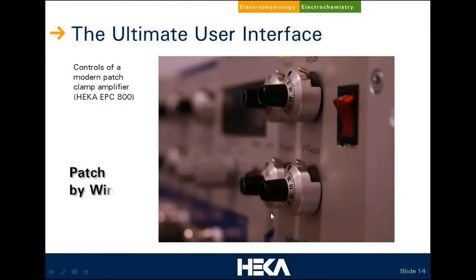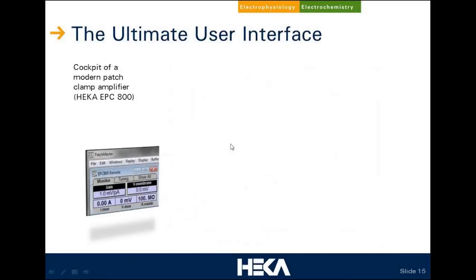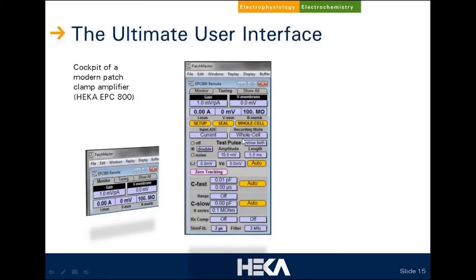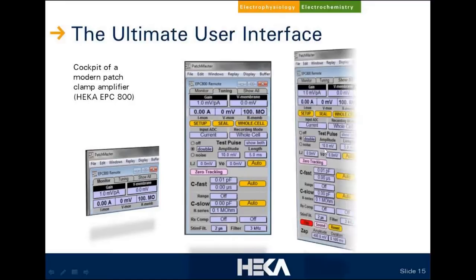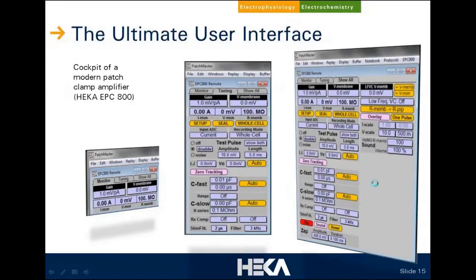Translating that to a patch clamp amplifier: patch-by-wire means you have what looks like an analog control with knobs and buttons, but it controls digital circuitry behind the scenes. That's the old-world interface. The new-world interface of that same amplifier is the cockpit of a modern patch clamp amplifier — the EPC-800. It comes in three flavors: a monitoring-only mode showing values like current, voltage, and membrane resistance; a tuning mode with whole-cell compensation controls; or the full mode where you see and control everything. The one decision you have to make before the experiment is: are you going to drive yourself or use the chauffeur today?